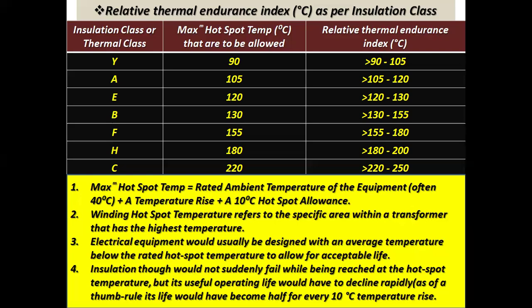Now, the maximum hotspot temperature must be equal to the rated ambient temperature of the equipment, often designed as 40 degrees centigrade, plus a temperature rise, plus a 10 degrees centigrade hotspot allowance. Winding hotspot temperature refers to the specific area within a transformer that has the highest temperature.